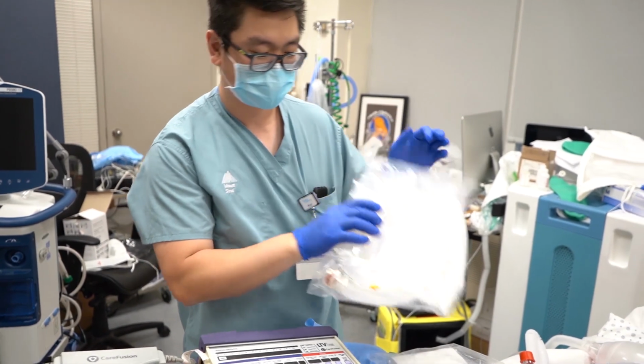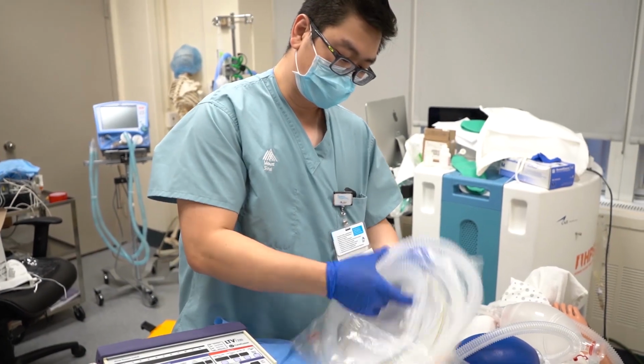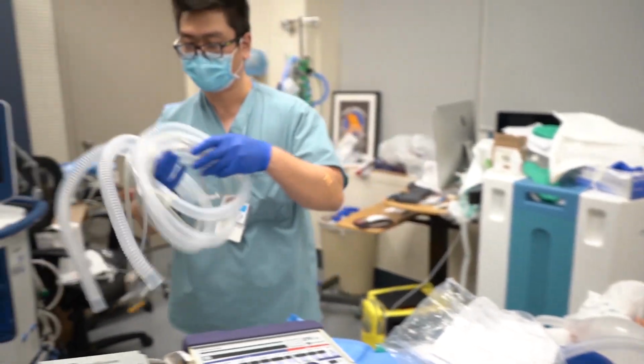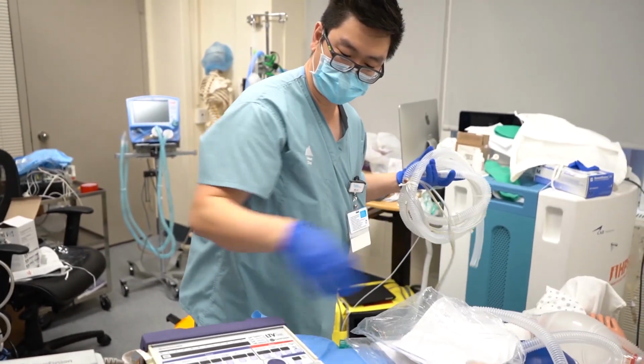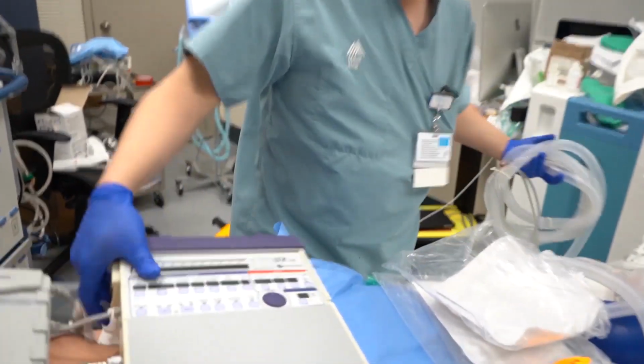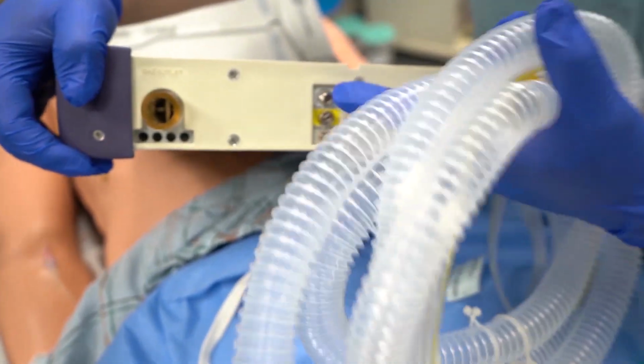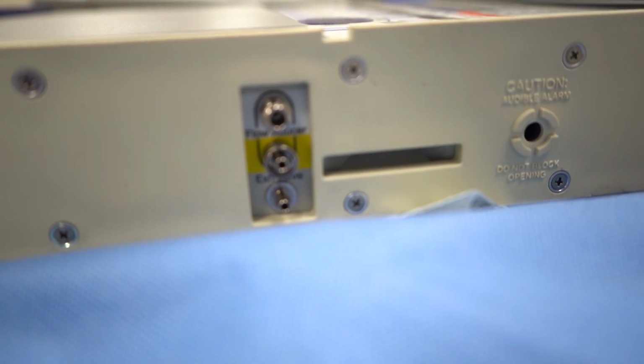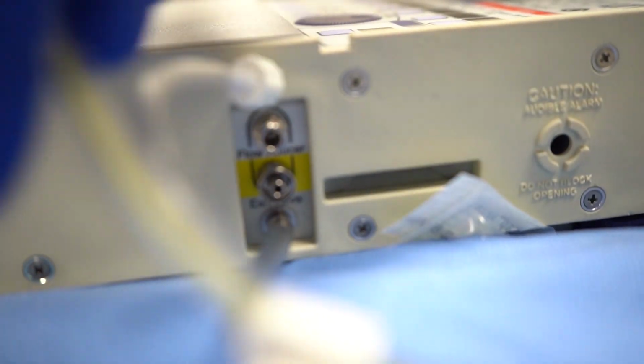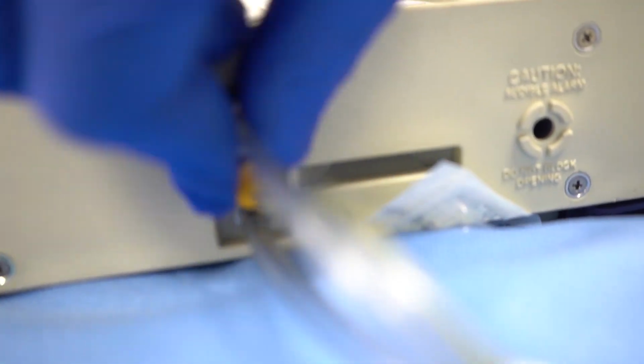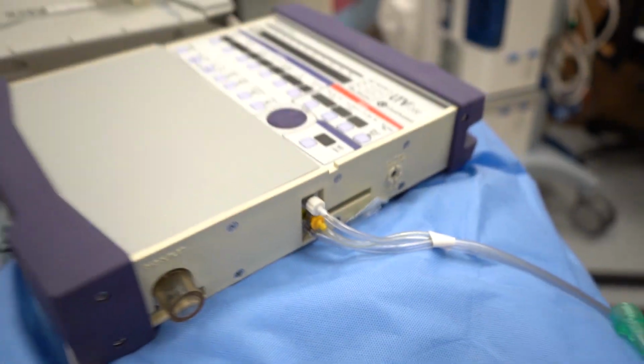So this is the circuit that's going to come with the LTV. There's a couple pressure lines and a flow sensor. And they all connect. They're all color coded on the side. It's kind of hard to see. They only fit one way. They each have their own separate connection. Can you see that? Let's put it down. So it's simply going to be clear lined for the pressure line, yellow to yellow, and then white to white. So just screw on.